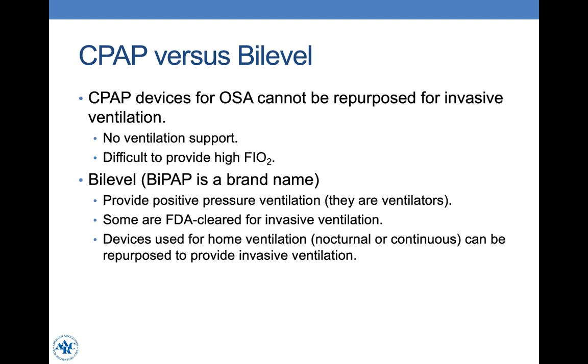Let's begin by discussing CPAP versus bi-level ventilation. CPAP devices intended for use in patients with obstructive sleep apnea cannot be repurposed for invasive ventilation. With these devices, there is no ventilation support and it is difficult to provide a high FiO2. Bi-level devices, however, can be used for ventilation. I would point out that BiPAP is a brand name and I will not be using that in this presentation, but rather using the term bi-level. These devices provide positive pressure ventilation — they are ventilators, whether used invasively or non-invasively.